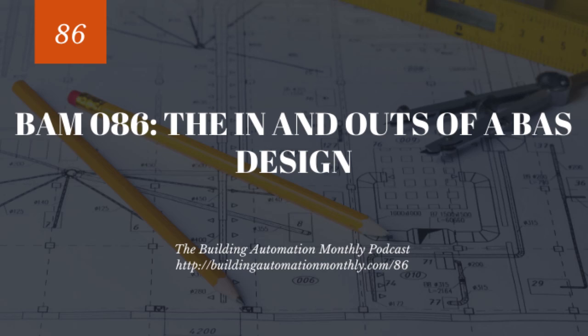Then you've got a controller drawing, which is going to show the controller. It's going to show the wiring, how it's wired and where it's connected to, like what device is connected to what input. You'll typically have a points list on the controller drawing as well. Oh, and on the system drawing, you'll typically have the sequence of operations, which is a text version of how the system's supposed to perform.